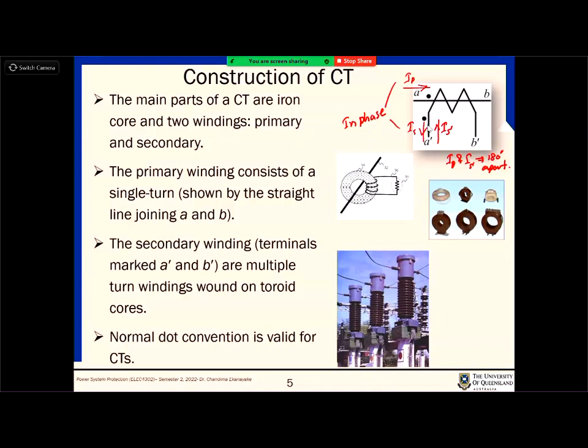Can you remember? What does dot convention mean? It is very important for CTs, because if you are connecting two CTs, especially for a differential application, then you need to remember what this dot means. The dot means that a current going into this dot in the primary circuit will produce a current coming out of that dot in the secondary. And these two are in phase. So if you mark the current going into the dot in one circuit, the current coming out of the other circuit, those two are in phase. So when you are doing the calculation, when you are connecting them, you have to think about in which direction they are in phase.